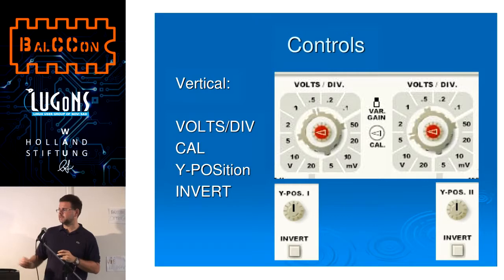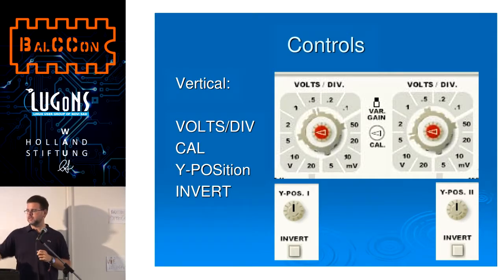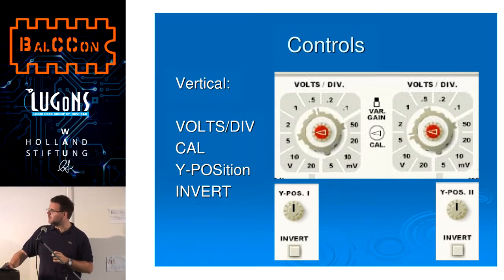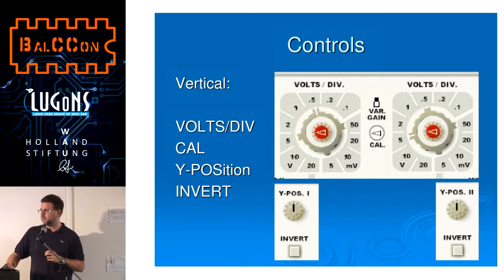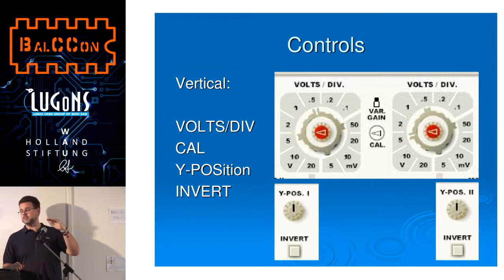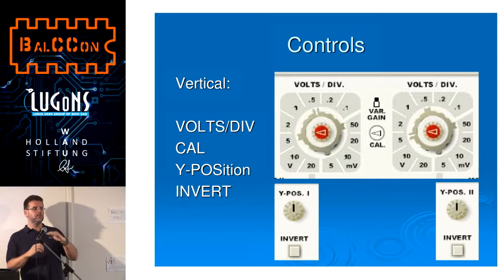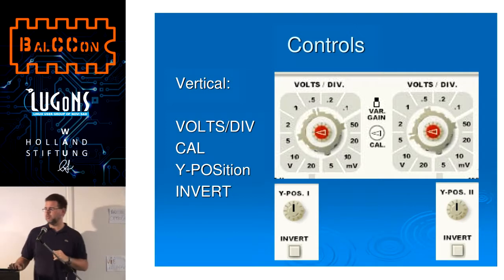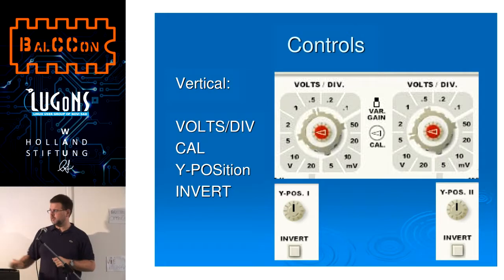You get two sets of controls, meaning you can represent two separate signals with a single time base. This is the waveform we're talking about — I've already explained how we determine frequency and amplitude. This is where we control volts per division for both signals. Y position means you can move the position of a signal up and down. If you're looking at two signals at the same time, you move one signal up and the other down so you can see both simultaneously. Invert means you can invert the input signal.